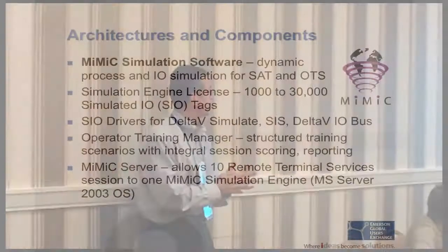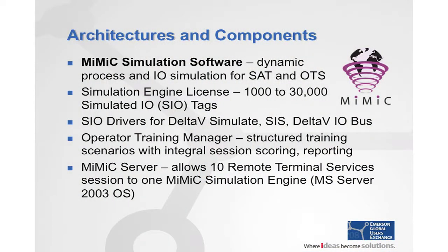The one thing that is missing is a dynamic simulation for the process I/O, and that's where MIMIC comes into play. MIMIC is a dynamic process I/O simulation package for software acceptance testing and operator training. MIMIC essentially comes in either through the I/O sub-system of the Delta V controller or directly as the models are assigned to the workstations, reads and writes to I/O values. It allows you to have dynamic I/O simulation and build process models to the level of complexity required for the application.